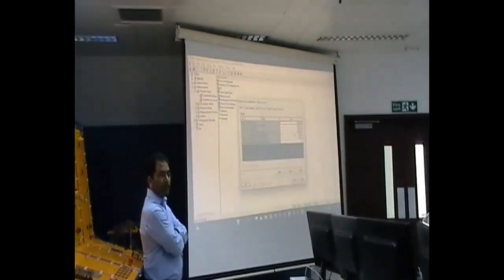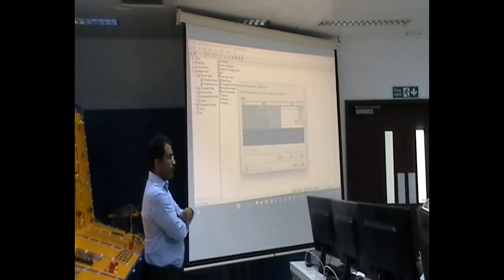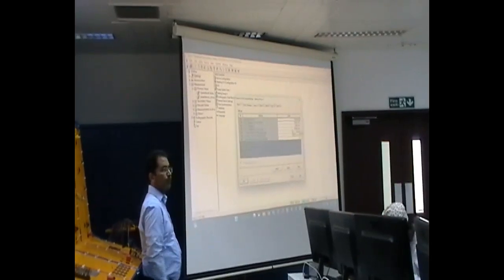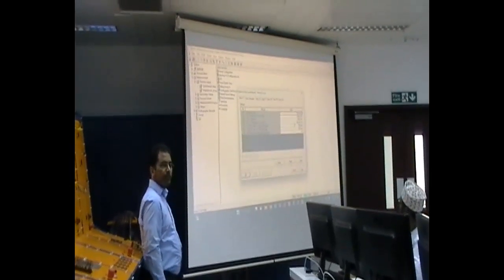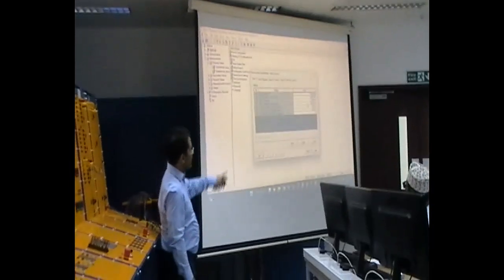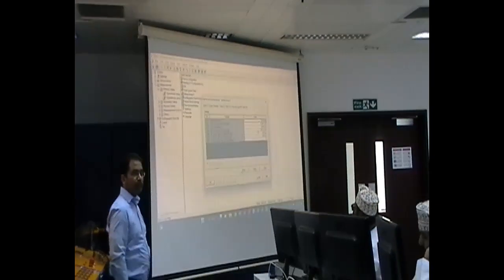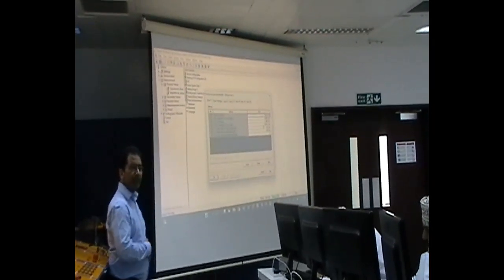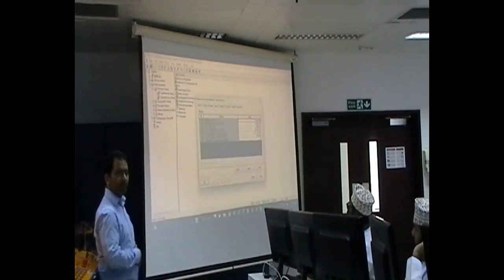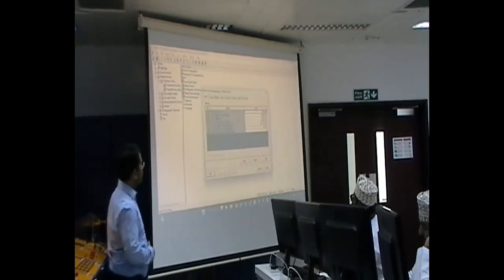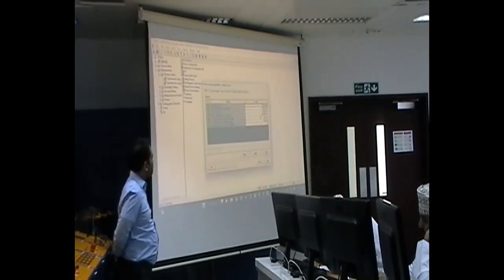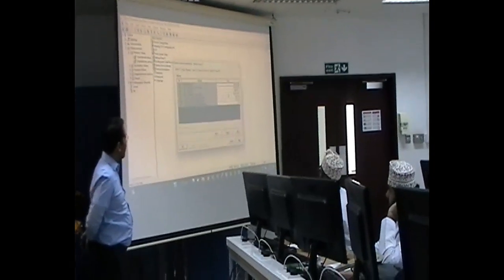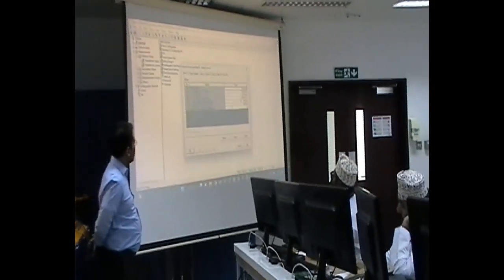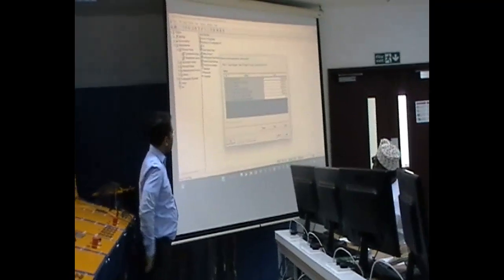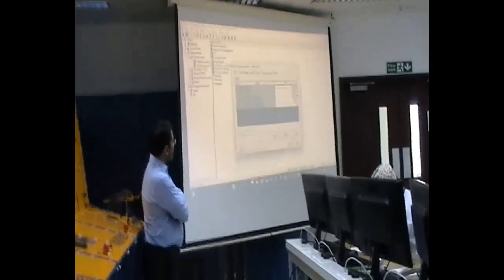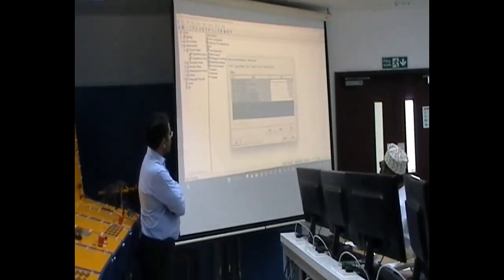You need to record this because later, once we are checking the relay, we need to compare the setting with whatever is coming in the test kit. Please record these values, please. Is it in secondary ohms? I presume yes. Yes. This is secondary. Resistance for phase to earth 26.3. This is zone 1.